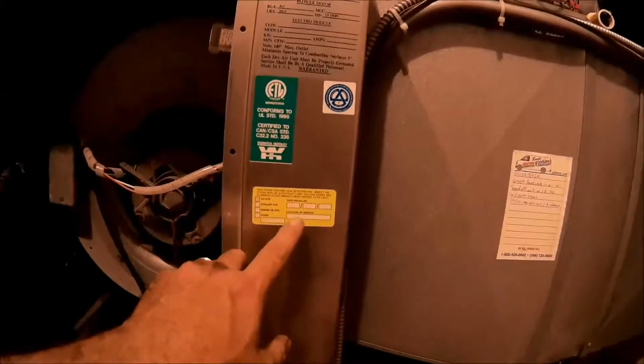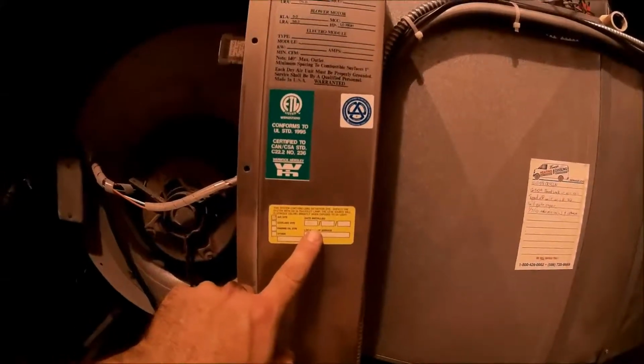Another contractor put some dye in there, and what I'm finding is right at the Schrader valve, you can see it's leaking. So we got to get that core removed. When I showed up here this morning, it was on lockout, so I'm thinking it's got a low charge. But let me get that changed out, get the gauges on it, make sure we got the right charge, and then see what it's doing.